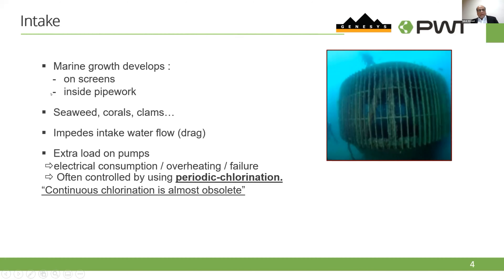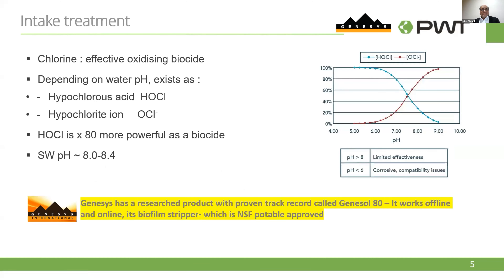This one is the Gold Coast intake system. In an intake system, you do periodic chlorination — nowadays there is no continuous chlorination. Chlorine injection is a very effective biocide. Depending on the water pH, chlorine can exist as hypochlorous acid or hypochlorite. As you can see in the graph, the higher the pH, the less effective the chlorine.